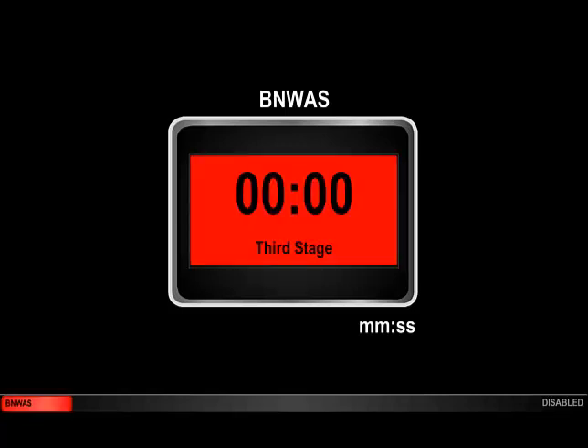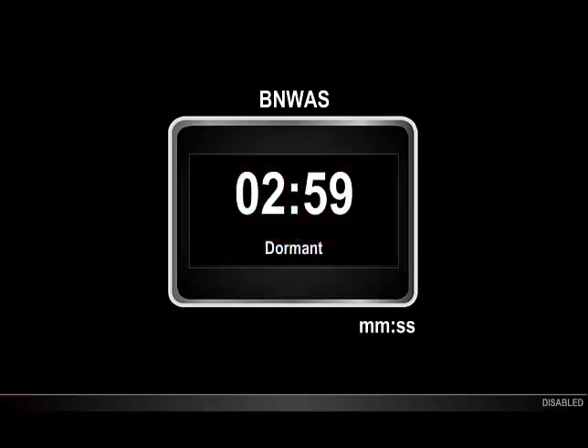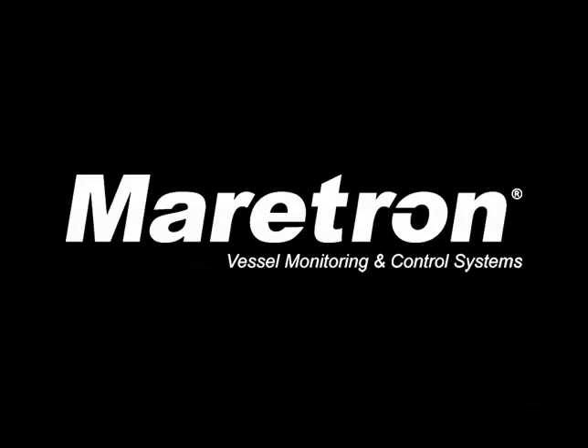After another 90 seconds, we enter the third stage remote audible alarm stage, and the third annunciator — perhaps in the crew's quarters — begins sounding in addition to the other two annunciators already sounding. If we touch the screen at this point, we reset the system back to the start of the dormant stage, and the entire process repeats itself. This concludes the video describing the operation of the Bridge Navigational Watch Alert System in the N2KView Vessel Monitoring and Control System.